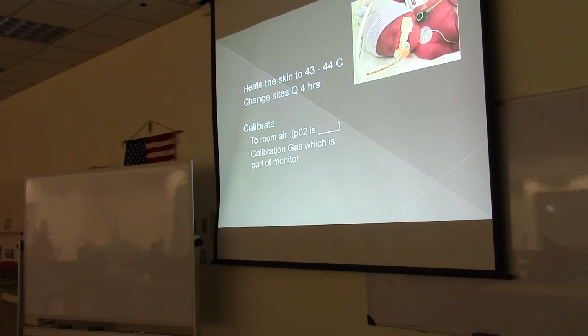All right, so when you're calibrating the transcutaneous monitor, you can calibrate it to room air. If you're holding the monitor in room air, what should the PO2 of room air be? 159 torr. Yes, very good. So you expose it to room air, it should say 159. If not, then you calibrate it to 159. And then there's also a calibration gas inside the monitor for calibration.